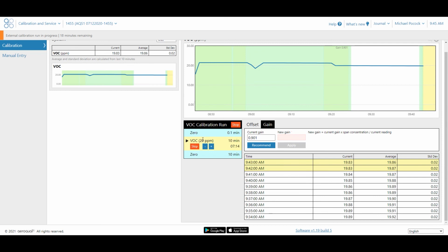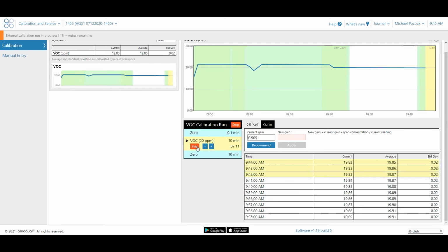So I would then just skip, and the next and final step, I would swap the cylinders over again, and just ensure that I am reading 0. So we've started with 0, we look at our span, and then the manufacturer recommends that you check the 0 again at the end. So that's how you do a full calibration.